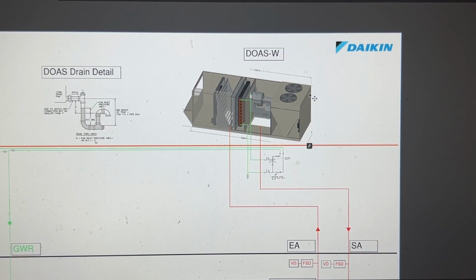Not on this project, but on another project where we installed a similar unit, we ran into an issue at startup because, with it being a self-packaged unit, I was under the presumption that we didn't have to add anything more, but we do need to add sensors for the static pressure as well as for the exhaust. So that would be one thing to make note of. Look at the wiring diagram and see if you do have a situation where the BACnet is all that's required. They just want to see it on the graphics. That you definitely want to put in. Make sure that we get that static pressure probe in there. Otherwise, that unit will not run. So that's the DOAS unit. Thanks for watching.